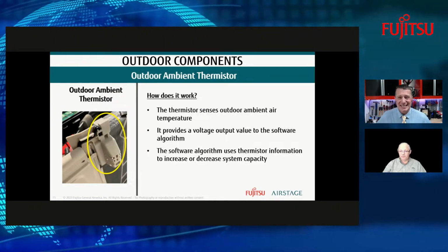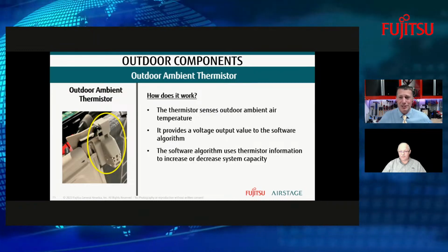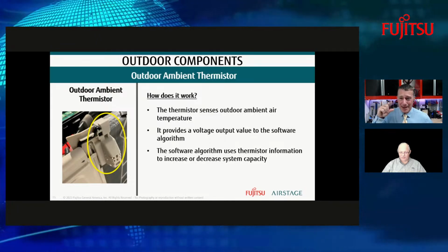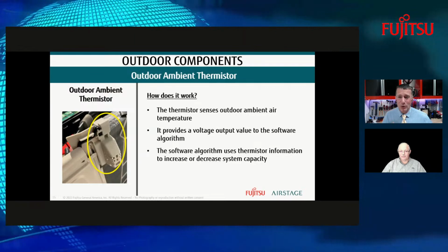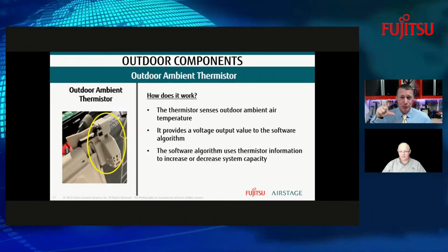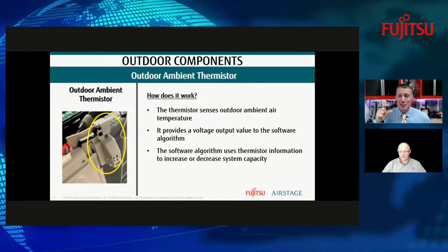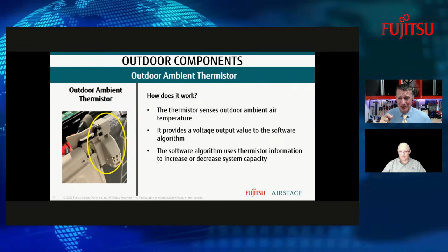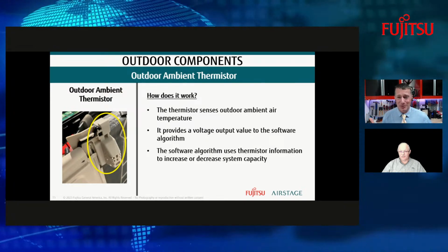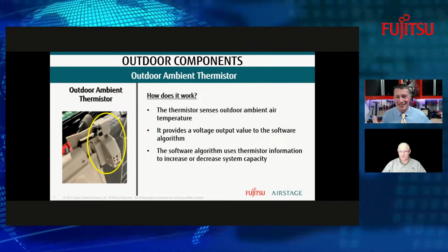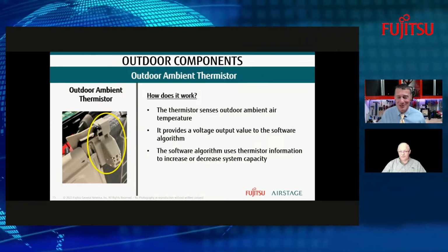Well, even think about things like defrost cycles. Look at a traditional heat pump that used to use a snap disc defrost, where we had a wide range of control that was only reading a refrigerant line temperature. Well, now we can utilize things like outdoor ambient thermistors to know what the temperature is outside in comparison to the temperature on my coil.